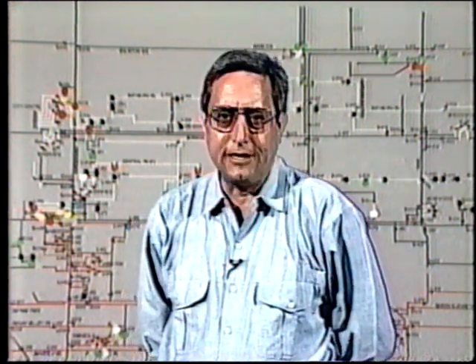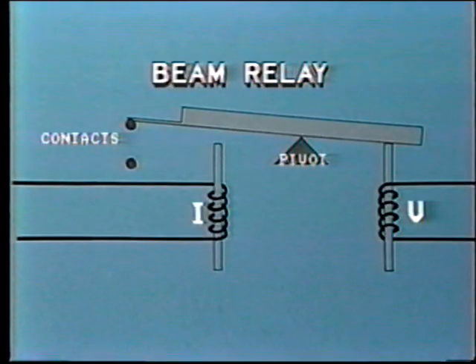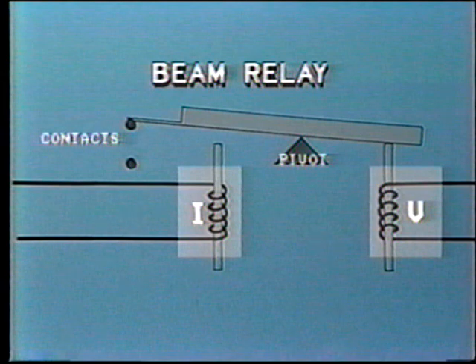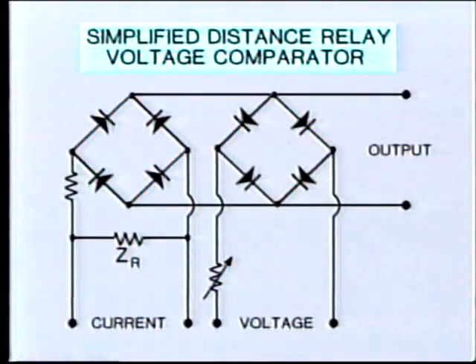Now let's take a look at distance relays, which operate essentially by comparing phasors of voltage and current. In the electromechanical relay, this is quite straightforward because the voltage and current circuits are separated. However, in the solid-state relay, as the circuits are interconnected, we must convert the two values to the same units, either both voltage or both current.